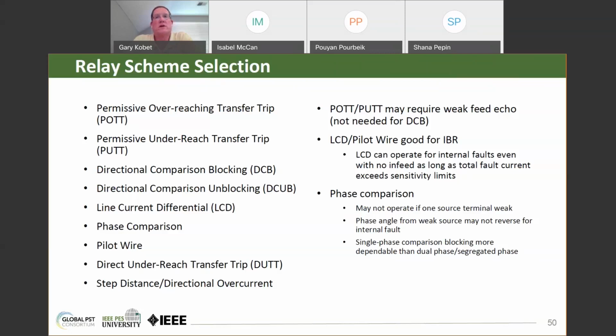Line current differential is actually really good for inverter-based resources because it can operate for internal faults as long as one end sees a strong source, as long as you have current above the sensitivity limits, I should say. And then some other things here about phase comparison schemes. More on that in just a second.